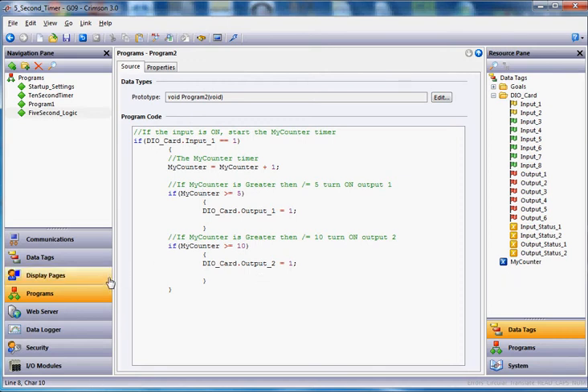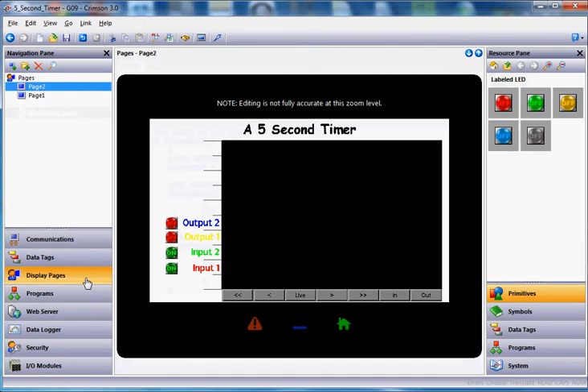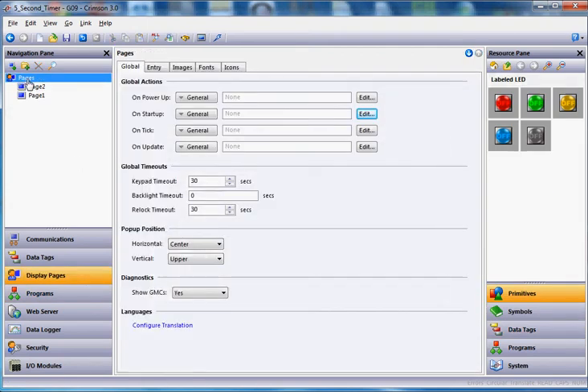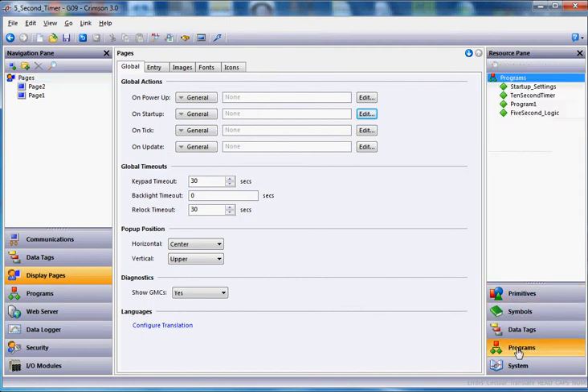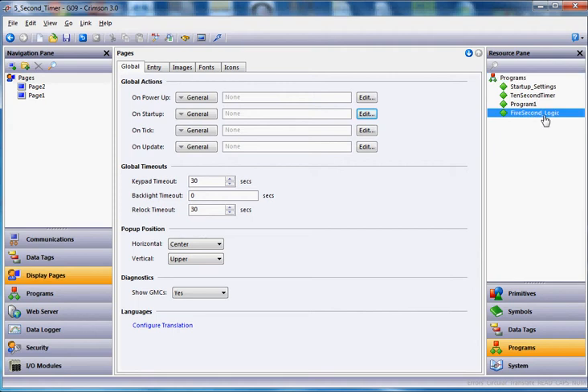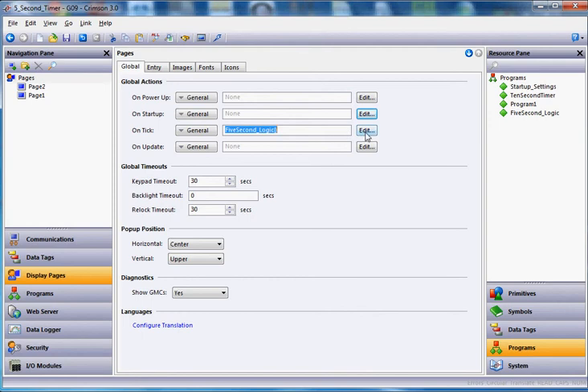Now what we're going to do, is we're going to go ahead and set up what needs to call this program. So I'll go to the left hand side, I'll click display pages. If I click up here on the word pages up on top, you get under the global tab, these four actions: on power up, start up, tick, and update. We want to call this program every second, so every second we'll call it. If that input stays on, it should count for us. So I'm going to go ahead and go over here, and I'll click on programs on the right side, and I'll drag my five second logic out here into the on tick field.